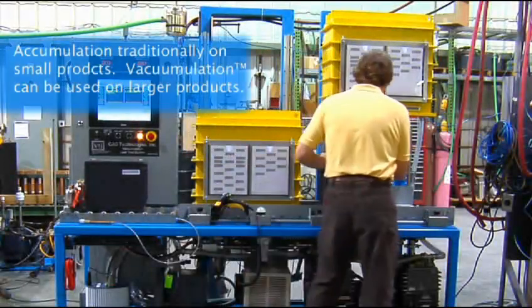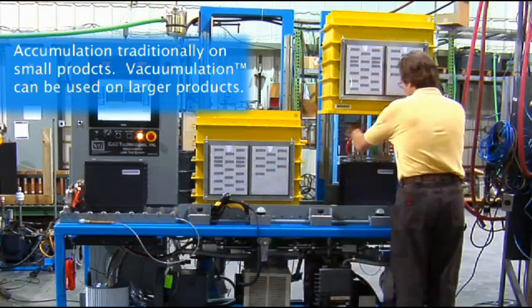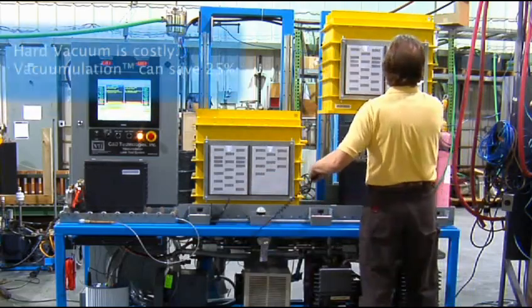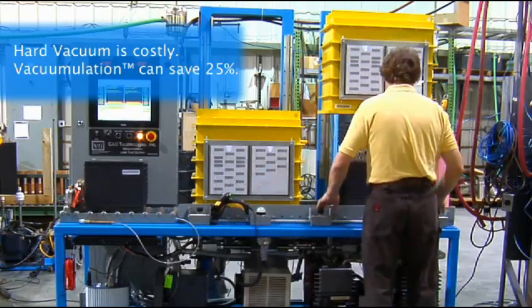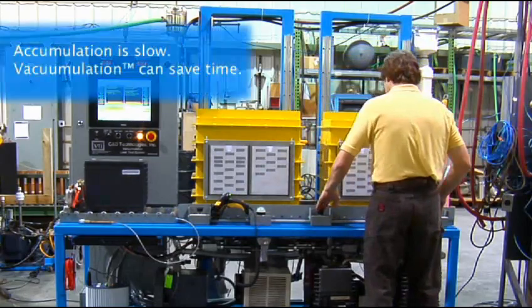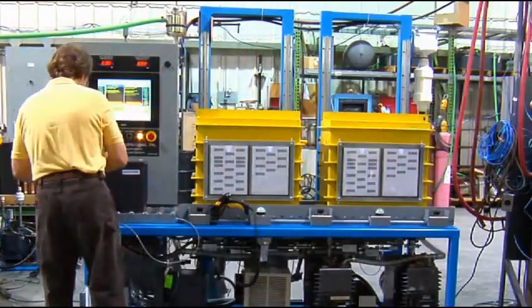Traditionally, accumulation leak testing methods have been used on small products, but now the use of vacumulation allows the size of the product to increase. Vacuumulation leak test systems are approximately 25% lower in cost than traditional hard vac mass spec leak detection systems. Vacumulation provides 10 to 100 times faster testing than traditional accumulation.